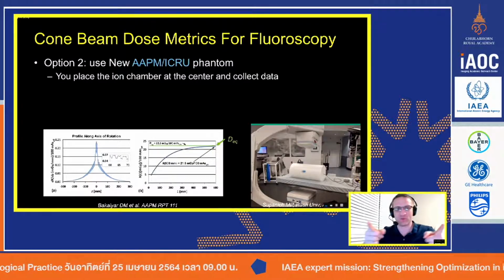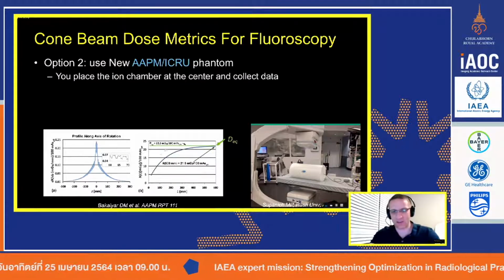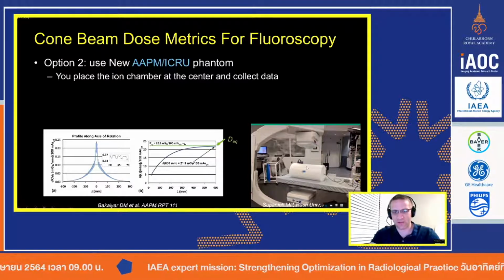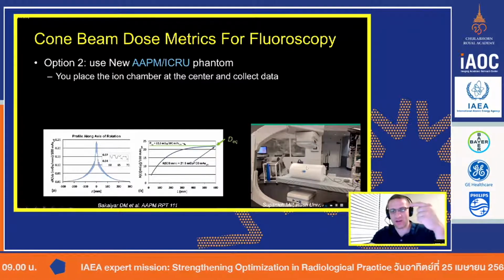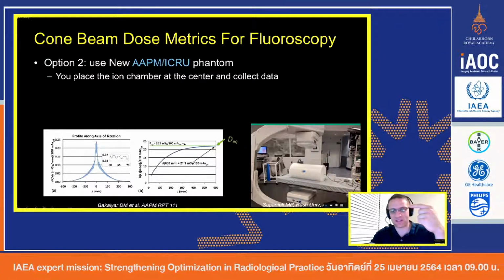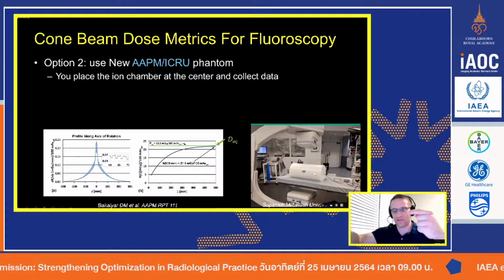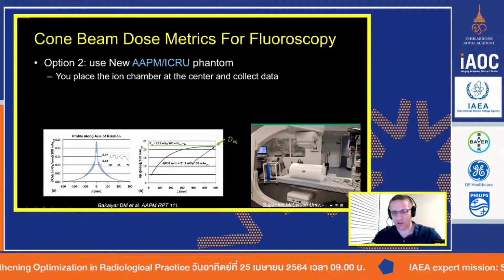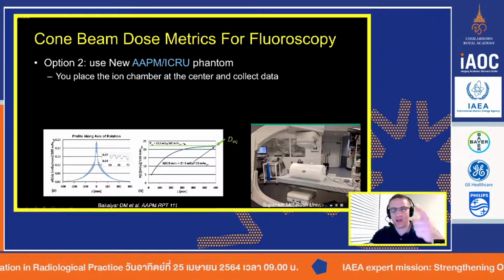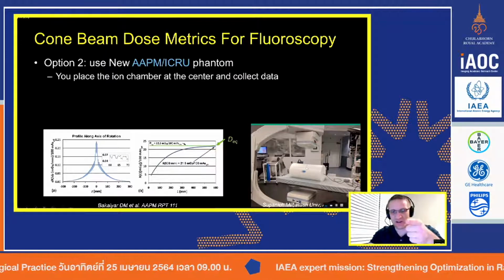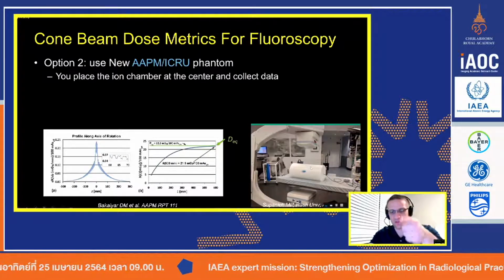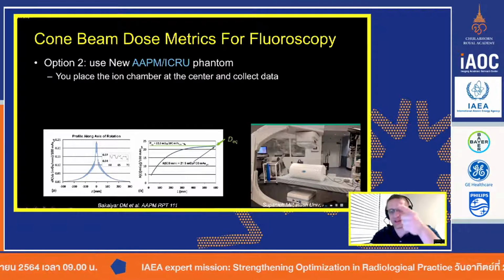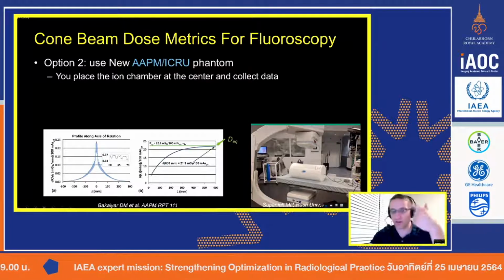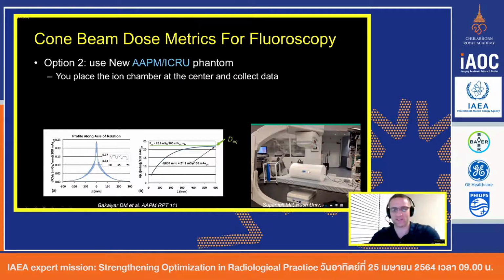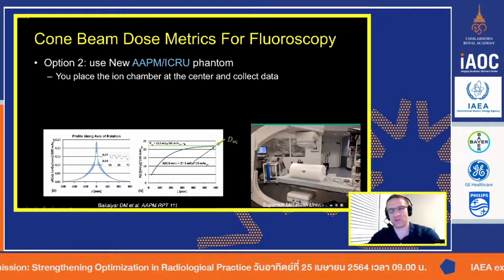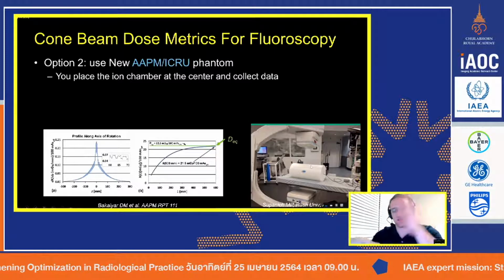So the other thing we do is we use a really small one, and we place it at the center of the phantom, and we do a spin. And then we move it 5 centimeters, 10 centimeters farther towards the end of the phantom. So we're going to start here and increment our way towards the end of the phantom. We stick it in the center, and then we spin, we move it 10 centimeters, spin, and we just keep going. It's going to take a while because it takes 45 seconds or 30 seconds to do a spin, to get it all set up and do it.